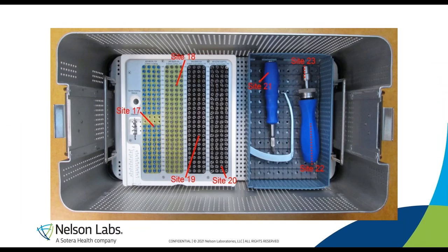Here are examples of areas we might choose for a SAL validation. You can see we've chosen a ratchet handle that has an insulated lumen — these can be very challenging for steam sterilization and are definitely something we would choose as an inoculation location in a tray such as this.